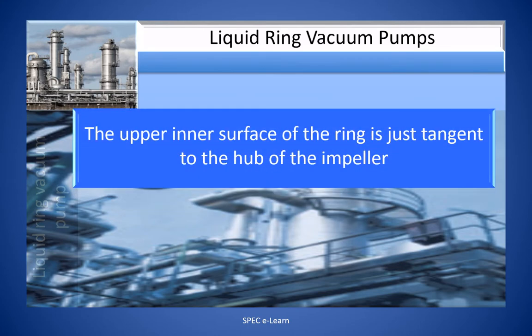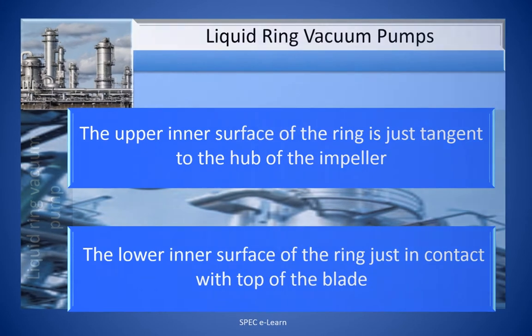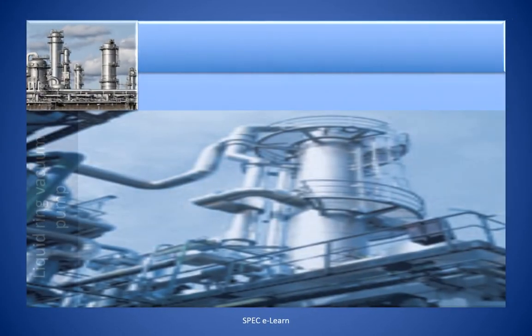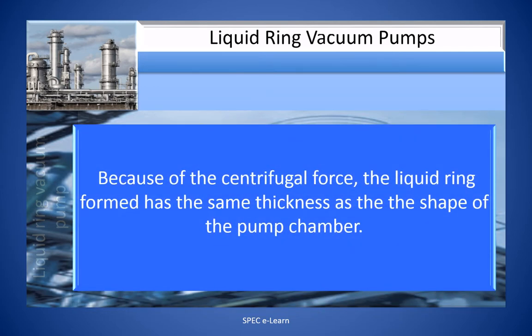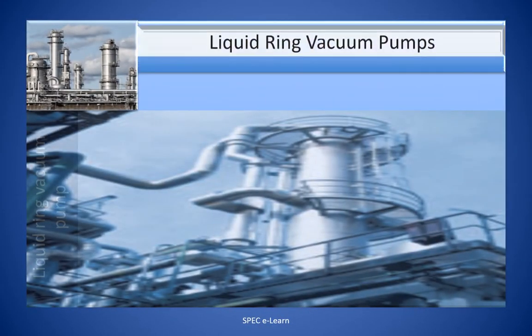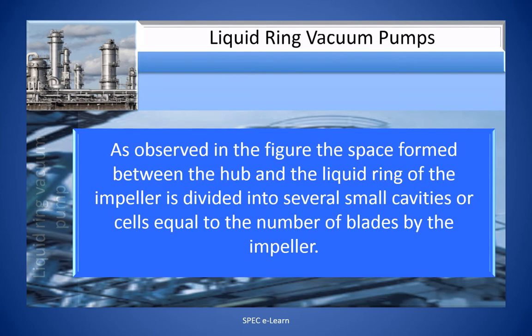The upper inner surface of the ring is just tangent to the hub of the impeller. The lower inner surface of the ring is just in contact with the top of the blade. Because of the centrifugal force, the liquid ring formed has the same thickness as the shape of the pump chamber. The space formed between the hub and the liquid ring is divided into several small cavities or cells, equal to the number of blades in the impeller.